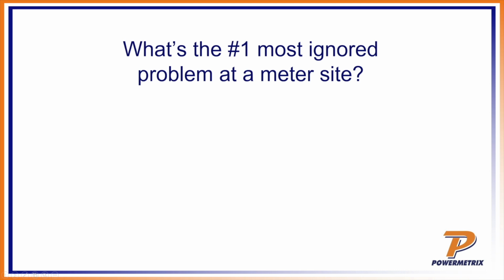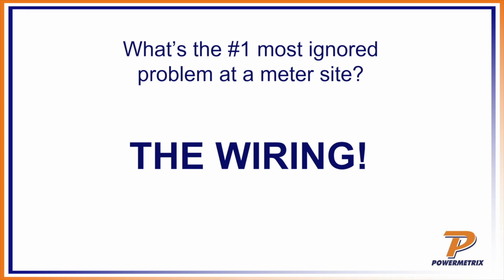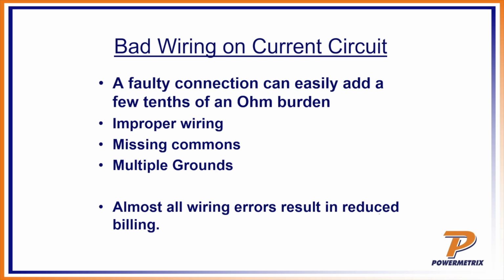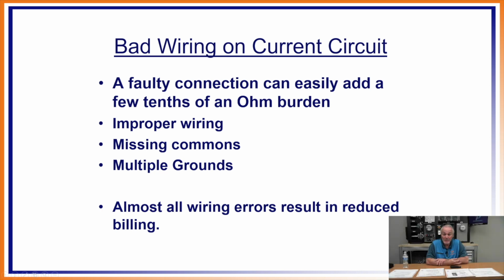According to Mr. Hudson, what is the number one most ignored problem at a meter site? Wait for it. The wiring. Why is that? Let's take a look. So bad wiring on the current circuit. A faulty connection can easily add a few tenths of an ohm of burden, either by improper wiring or improper connections. If we didn't squeeze them on there tight enough, or if I've got some missing commons or multiple grounds. Remember, we don't want multiple grounds in there if we can avoid it. Almost all wiring errors result in reduced billing. And you're thinking, a few tenths of an ohm, so what? Well, let's take a look at that.